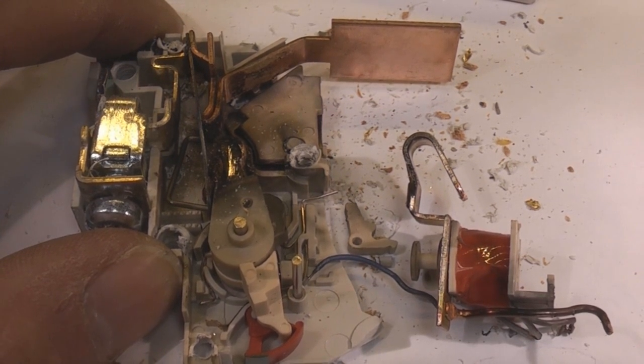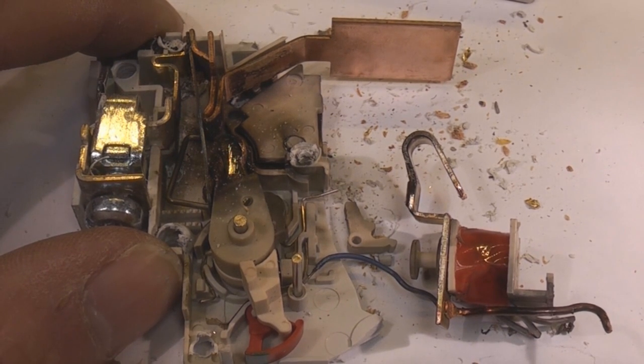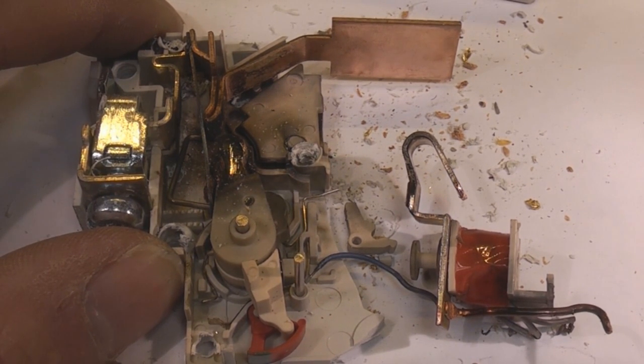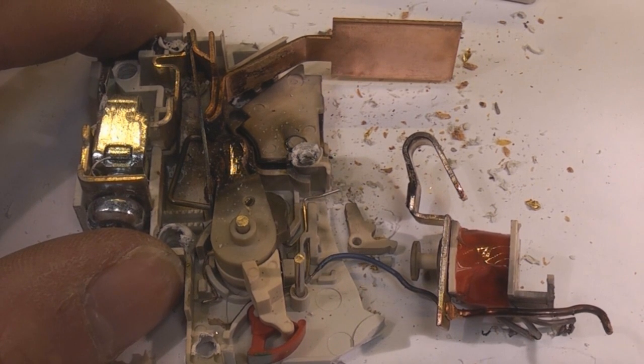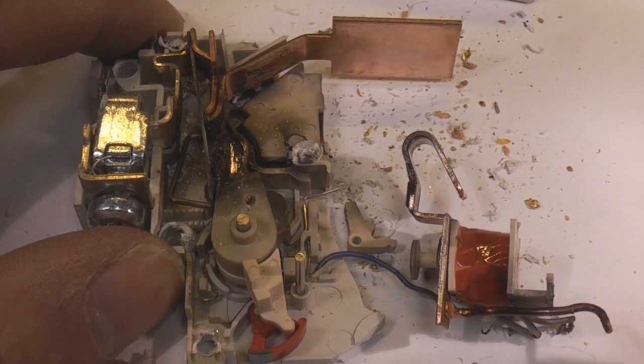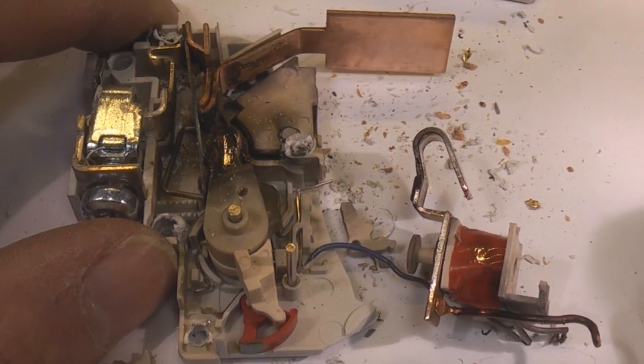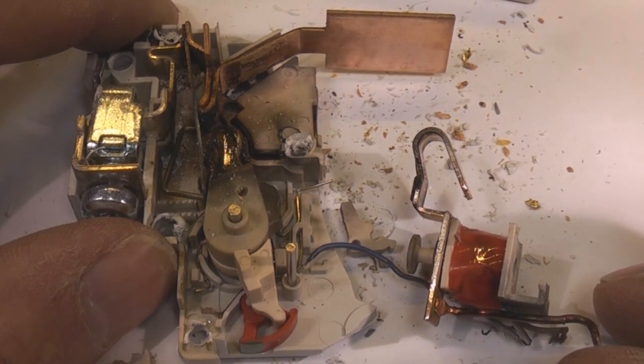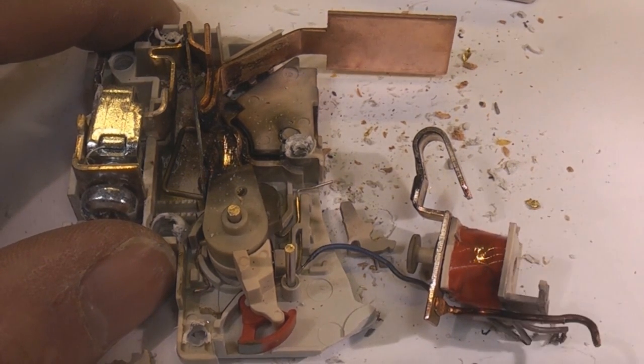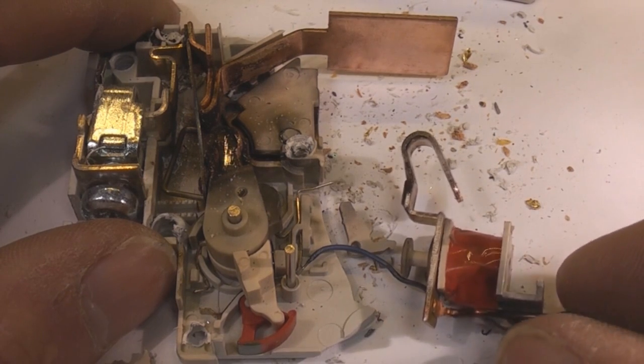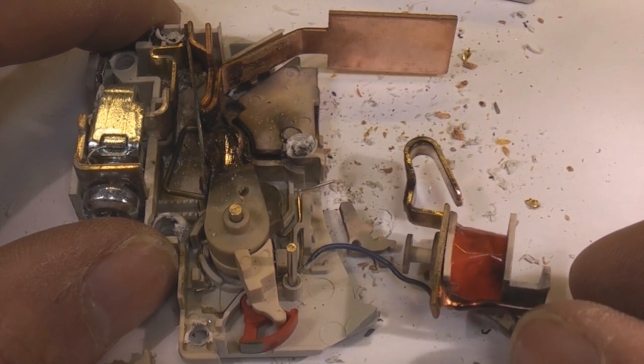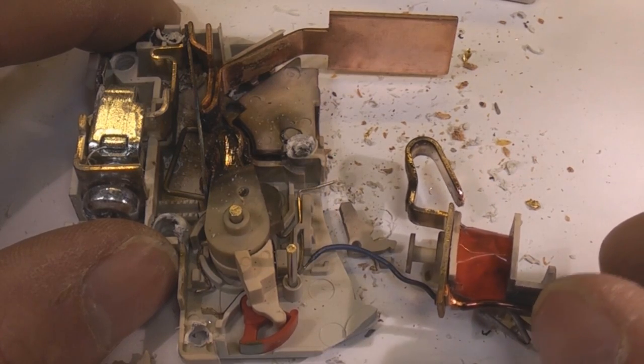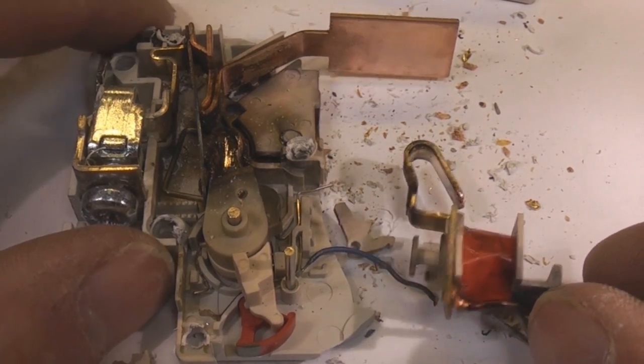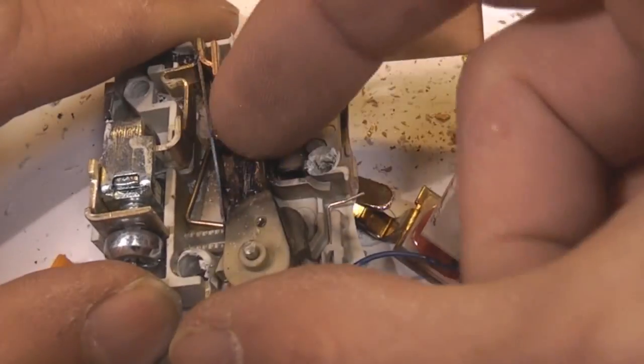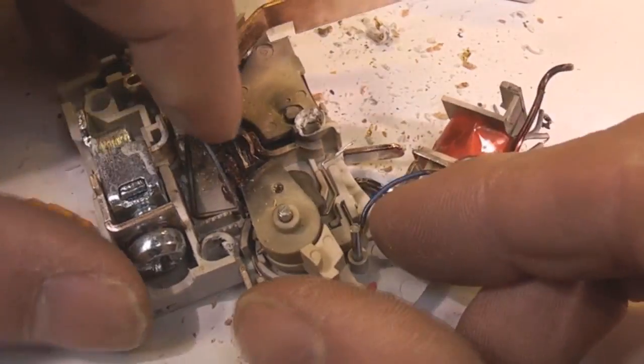That's pretty much a mechanical disintegration, not an electrical one. It's purely the forces that are set up by that massive magnetic field that just physically tear it to pieces, and obviously as it's coming apart the pieces will then maybe arc to some extent, but the primary destructive force is purely that magnetic mechanical force, which is difficult to measure, but I'm sure it would be in the range of thousands of amps within microseconds or so. So extremely high, generally fairly ridiculous.